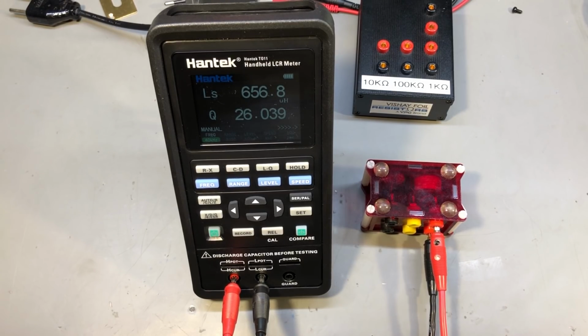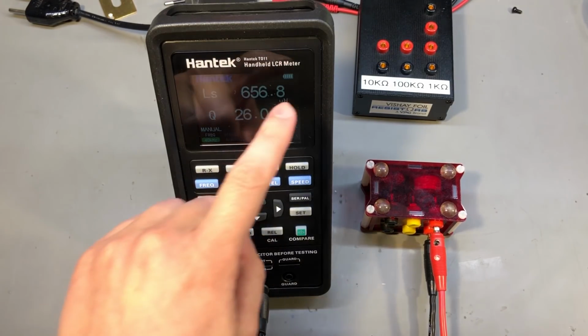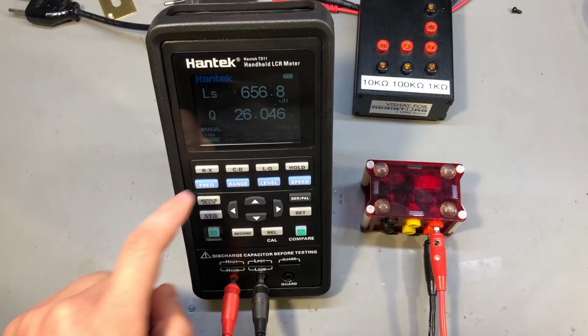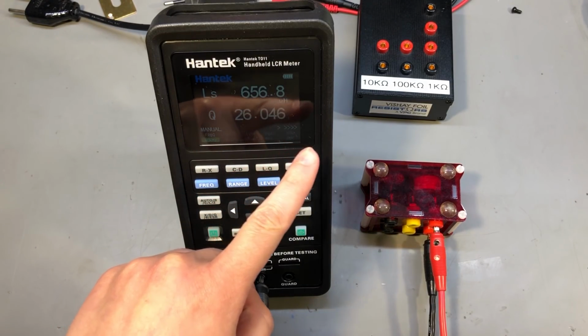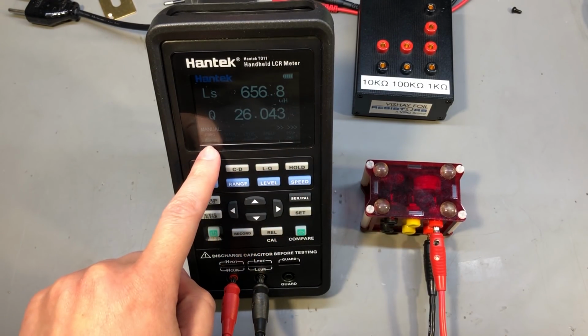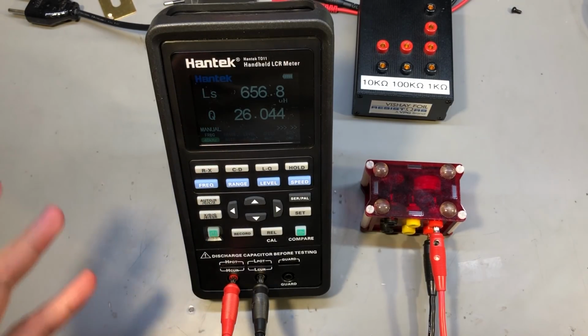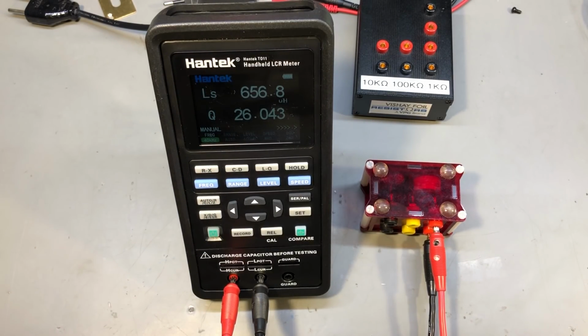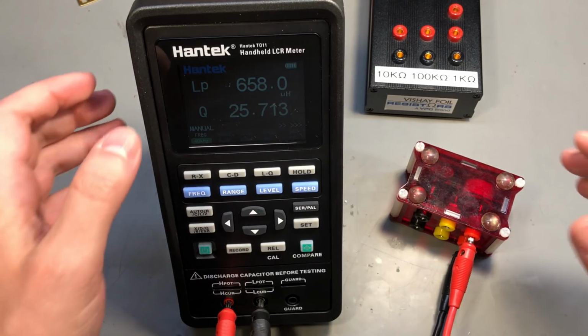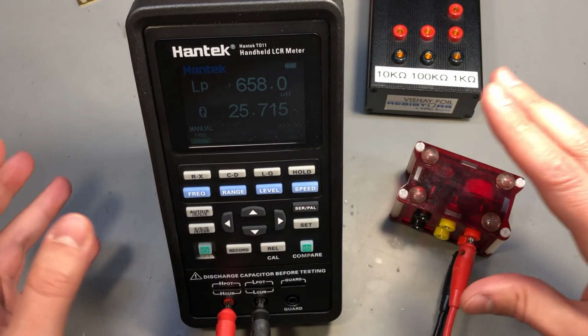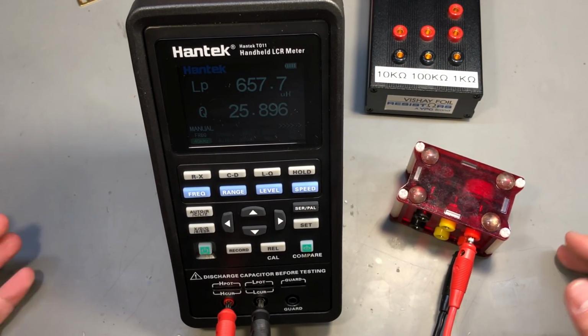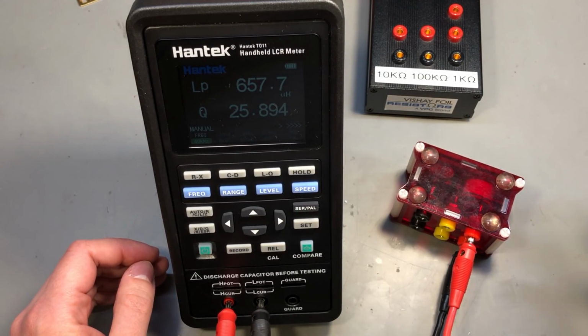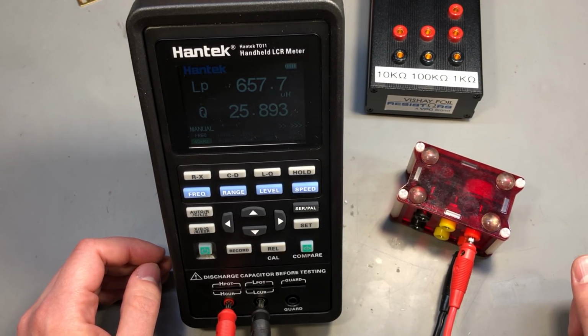As for the inductance measurement, we should be seeing 656.9 microhenries. So we are only one count out, but I should mention I switched to serial measurement and a frequency of 40 kilohertz to get the best results for this measurement. So it's all about having the right settings on the test instrument to be able to get accurate results, and it takes a bit of practice and reading of that app note that I mentioned to figure out how to do this properly.